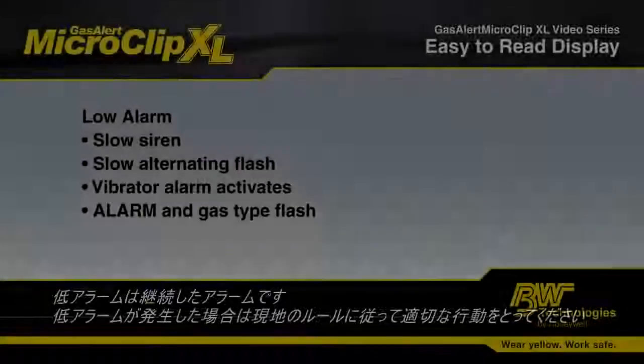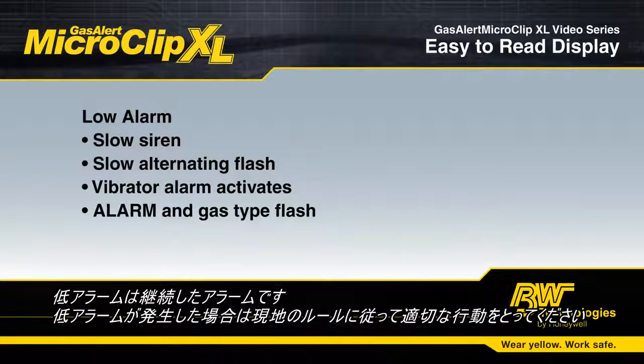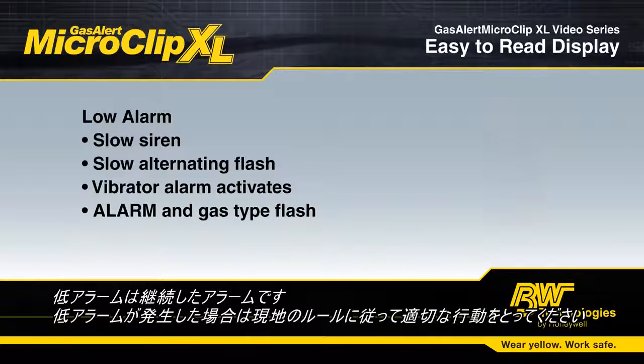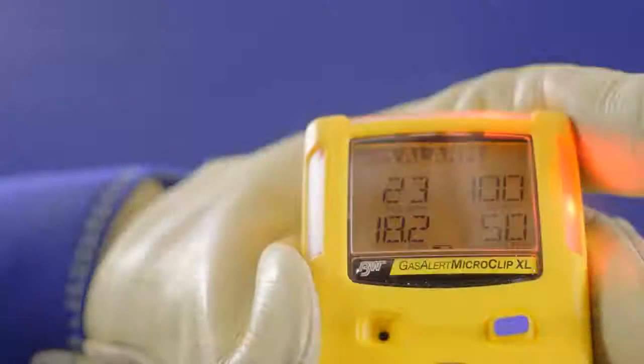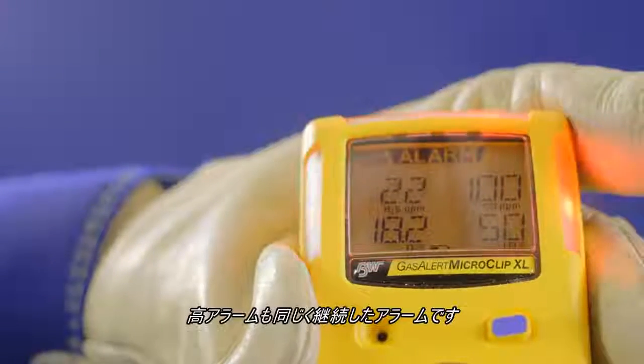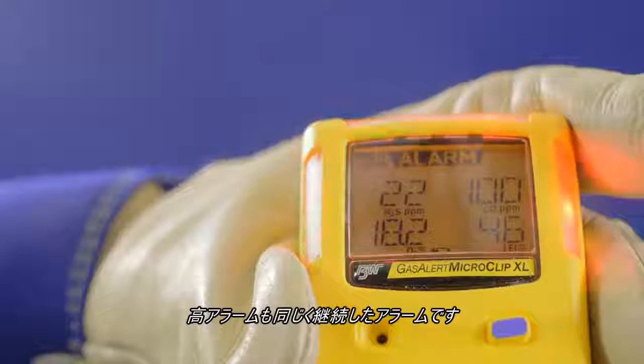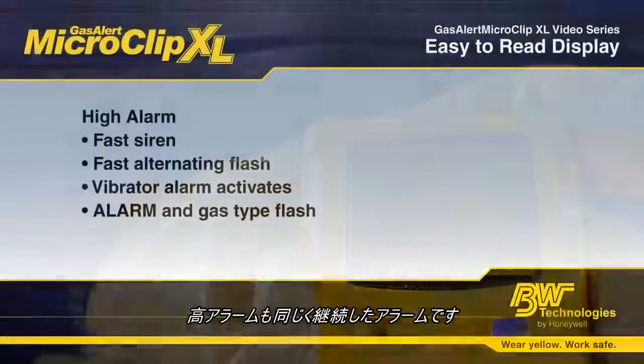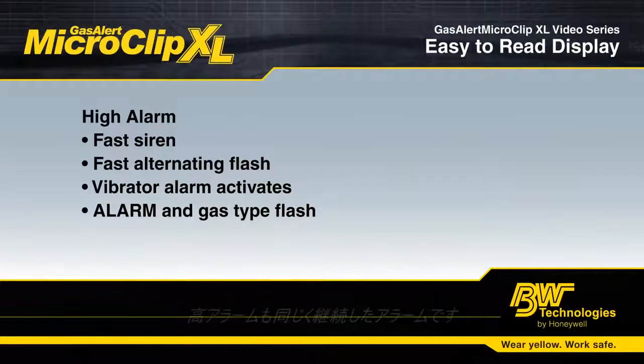The alarm type will also appear. Low alarms are instantaneous alarms. Take appropriate actions in line with your on-site procedures in the event your detector goes into low alarm. High alarms are also an instantaneous alarm and are a secondary warning level.